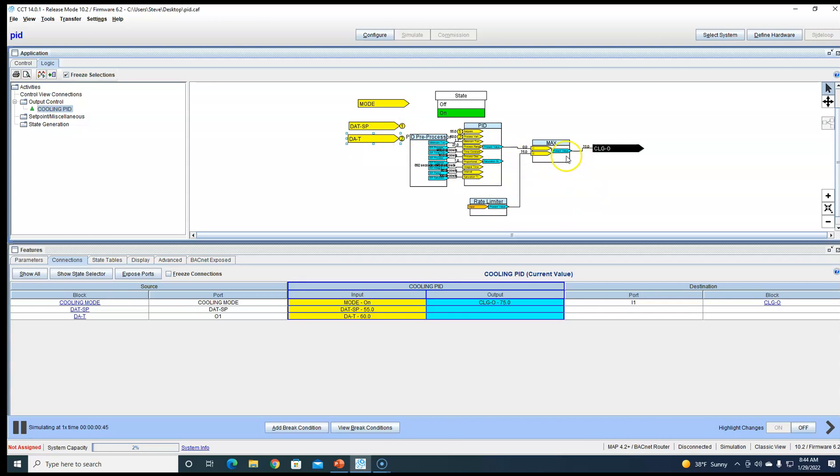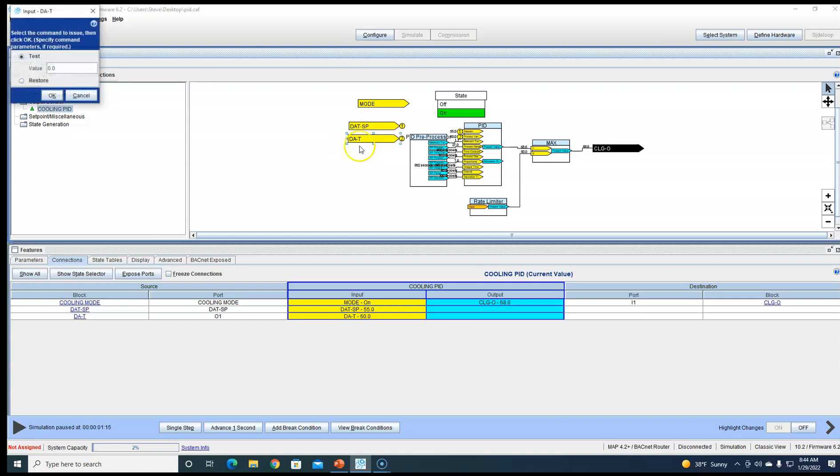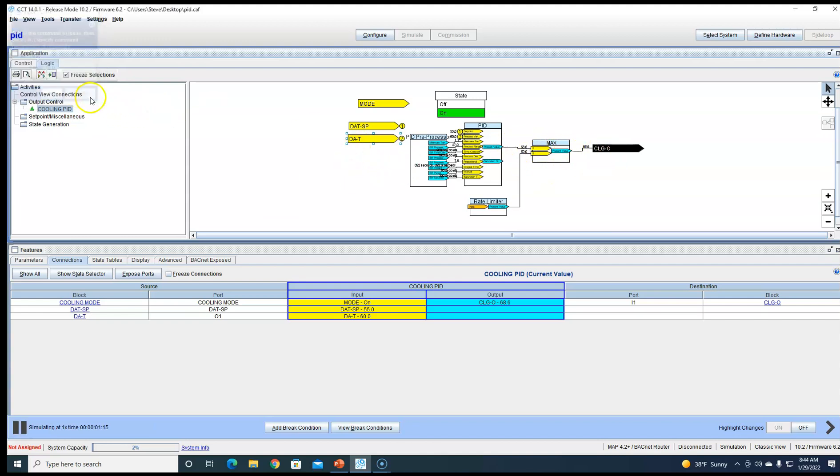Now we can do this at like 60, and it will only ramp down to whatever the PID's putting out because this max block. So whenever the PID puts out more than the rate limiter, that's what's on output. Boom, now we're outputting more than the rate limiter, so now the PID actually took over. So now you're going to get those super high temperatures in your chill water system if you're using this as a max and starting up at a hundred.